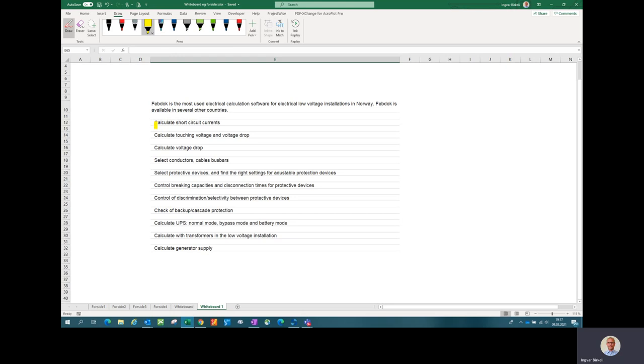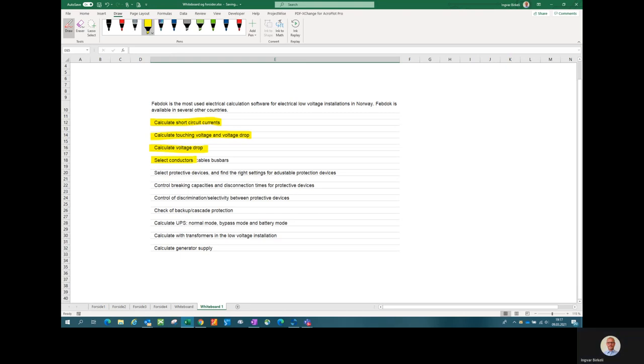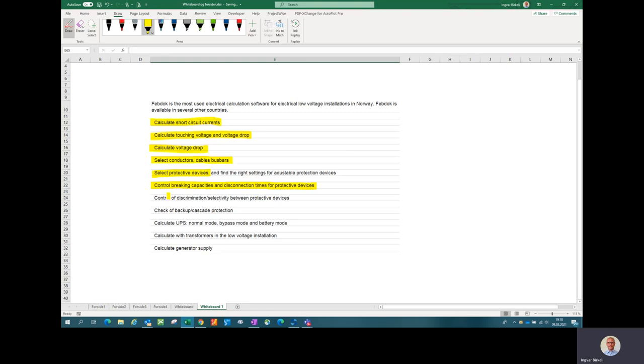Febdok is the most used electrical calculation software for electrical low voltage installations in Norway. Febdok is also available in several other countries. What you can do in Febdok is a lot of things. You can calculate short circuit currents, calculate touching voltages and voltage drop. You can select conductors, cables and bus bars mainly. You can select protective devices and find the right settings for adjustable protection devices in circuit breakers and motor protection. You can do a control of breaking capacities and disconnection times for protective devices. You can do a control of the discrimination or selectivity between protective devices.